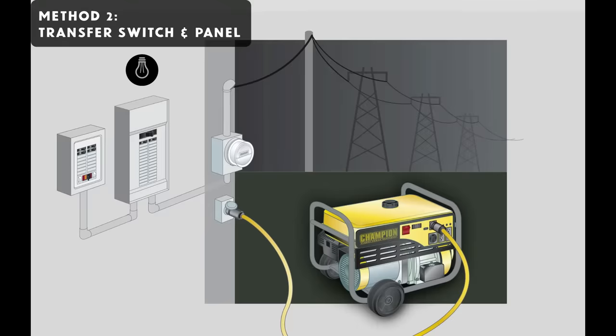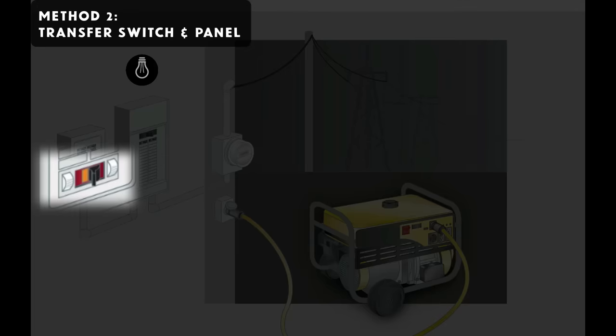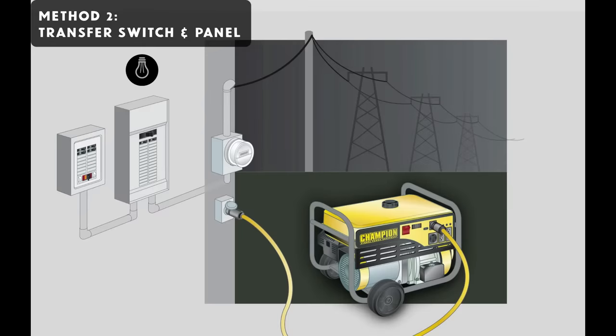First on the generator side and then the port side so that it can all connect together. And then you start up the generator. Now, at this stage, you still won't have any power in your house, and that's because of this thing here, the actual transfer switch. That switch connects either the grid to your home circuits or the generator to your home circuits, but never both at the same time. That's why legalities matter so much in this regard. If your generator were able to connect to the grid, it could feed power back into the power lines here, and that would endanger line workers who aren't expecting power to come from people's home generators when they're working to restore power.